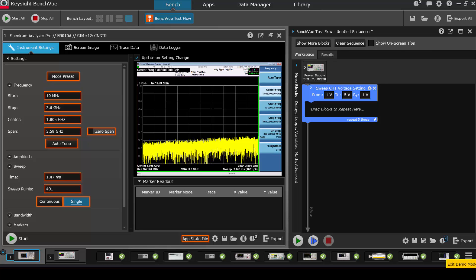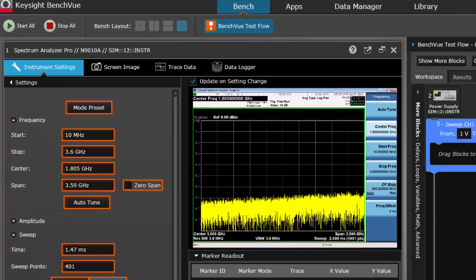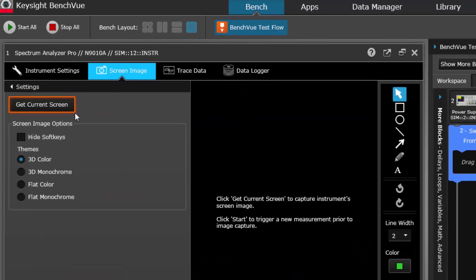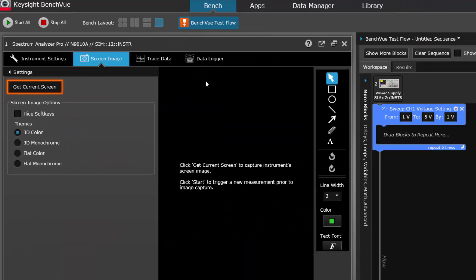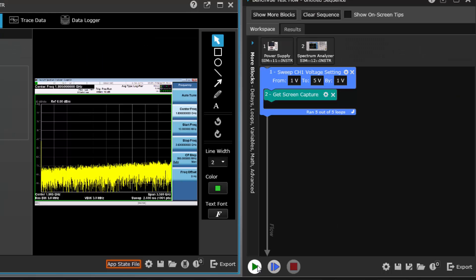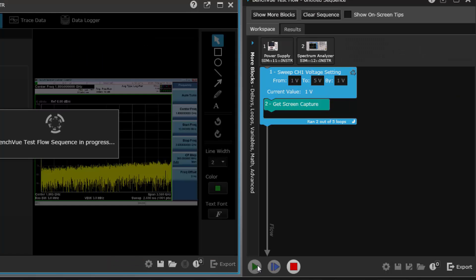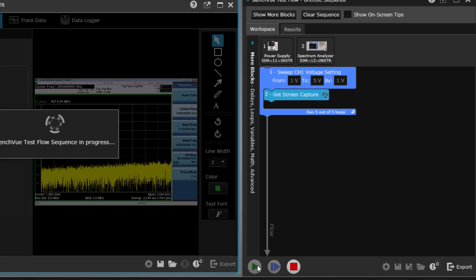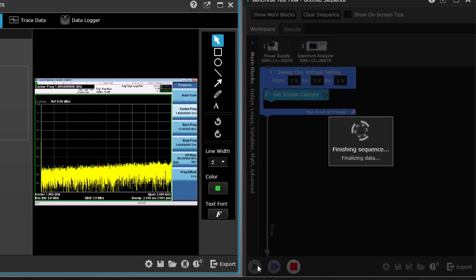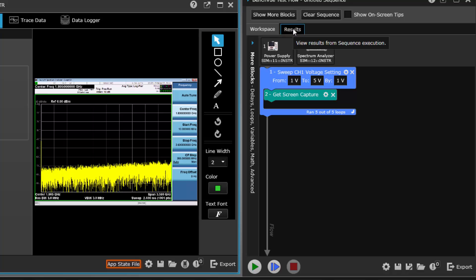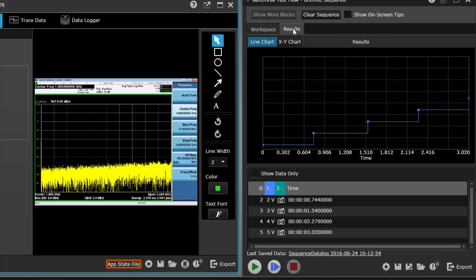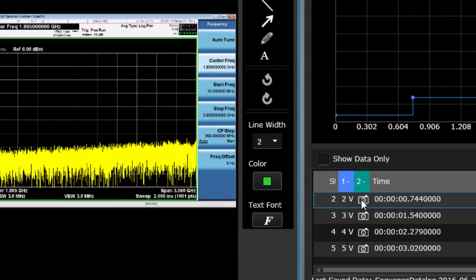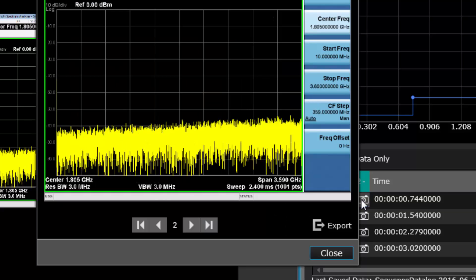In comparison, using any other tool would require you to figure out how to programmatically connect your instruments, get an IEEE 488 binary block, then convert the binary bytes inside your programming language to a picture file. In other words, a lot more work. In a few moments it took me to say those sentences, I was able to get those screen captures and analyze the data.